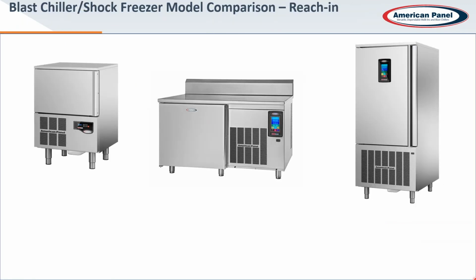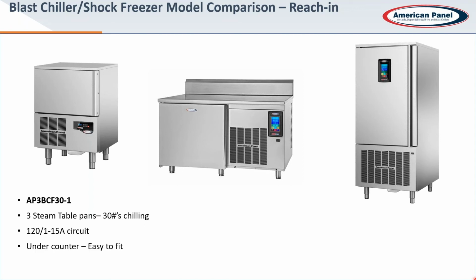Let's take a look at a comparison of some reach-in model blast chillers and shock freezers. First up, on the left-hand side, you're going to see our smallest unit. This is an AP3 BCF 30-1. The -1 on this unit designates it as a 120 volt connection. 3 steam table pans, 30 pounds of chilling capacity, again relating back to the designation and the model number there. Like I said, 120 volt power. It only needs a 15 amp circuit, so it can go anywhere. It can go under the counter. It's small enough to go under counter in a kitchen.